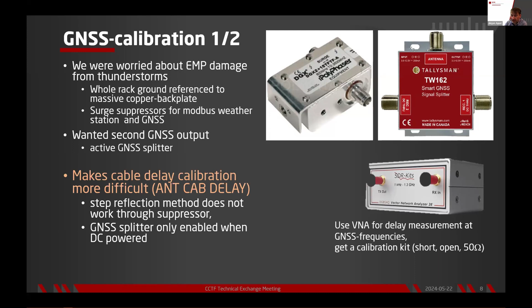The second part is, once you have everything installed, there's the 1 pulse per second coming into your pulse distribution amplifier. 1 pulse is coming out to the GNSS, and the next input, number 2, is our UTC DFM reference point. And it's important that you also think about how the circuit diagram of that looks. Our frequency distribution amplifier has a 3.3 volt output with an impedance of 13 ohms. That's less than a typical 50, but the advantage is that it can drive TTL signals into 50 ohms, which is really nice. On the other hand, that means it makes reflections if the load isn't 50 ohms.